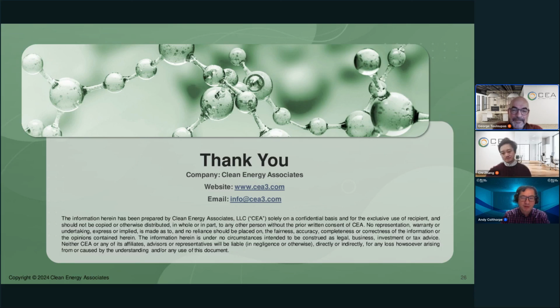I think there was a case where a BMS cable path was improperly designed, and there was a thermal event during our FAT. It's quite rare, so the fault would be more on the manufacturer rather than design. We did a root cause analysis, and then there was a design change. It's very rare because products go through a very long qualification, evaluation, and validation process before mass production. There's a big risk if this isn't done properly.